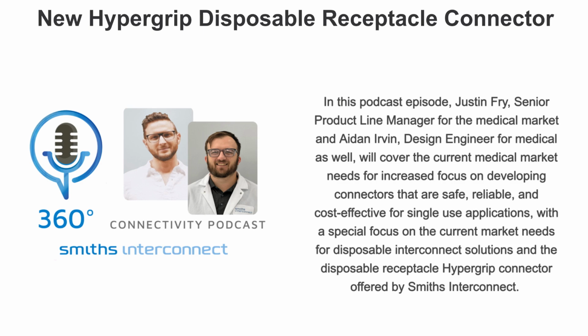Some of our competitors have 5 or 10 mates, some as many as 20. We have a cycle life of at least 30. The breakaway design, as I mentioned, is critical. We want to make sure that any pulling force that comes to that disposable results in the connector disengaging and not staying in its mating side, because we don't want to be pulling on parts or devices that are inside the patient. We also leverage a lot of our existing Hypergrip documentation and test reports. We did redo test reports for the parts of the connector that were impacted by the changes we made to accomplish the disposable. But again, we leverage what we know about the Hypergrip's long-term success to make this a very easy to adopt solution for our customers.